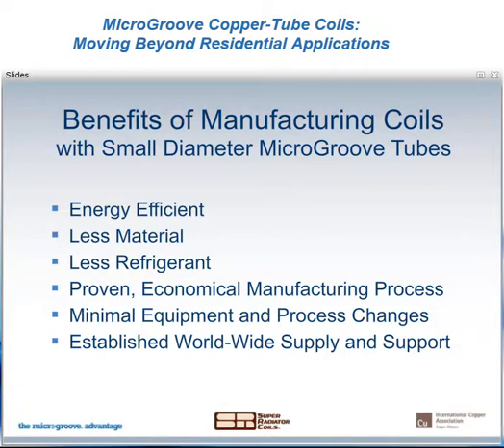As a result of the increased surface area from smaller diameter tubes, plus the reduced boundary layers, we have higher performing, more efficient heat exchangers that use less material and less refrigerant. And in a minute, we'll see how manufacturers like Super Radiator Coils can use these advantages in different ways to solve various problems that their customers come to them with. The manufacturing process for MicroGroove coils is a proven process and it's been in use for a long time. And using smaller diameter tubes does require some tooling changes and process modifications, but these changes are minimal, and manufacturers are finding themselves better positioned now to compete in a market that's always demanding more performance for less cost.